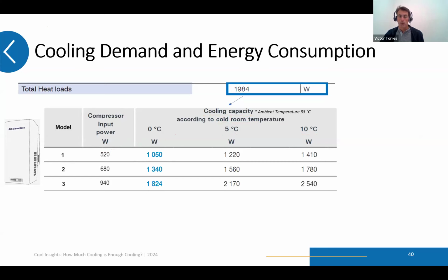In our case, we need 1,900 watts for our cold room in the worst case scenario, when the ambient temperature is 35 degrees. By the way, the manufacturers also provide the cooling capacity based on an ambient temperature. This is also important to consider. If the ambient temperature is low, then the cooling capacity will be higher, as we are going to see in a minute. Next slide, please.